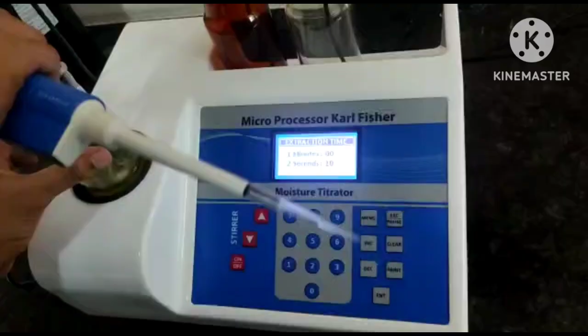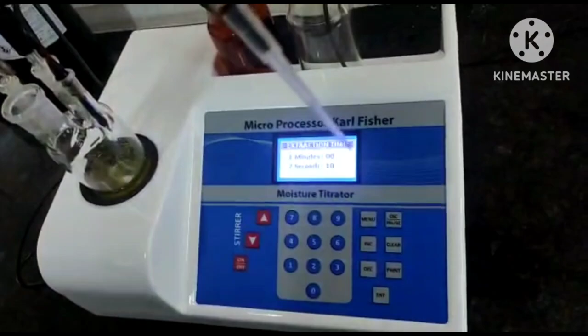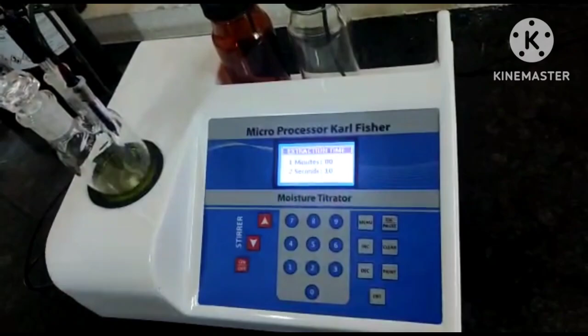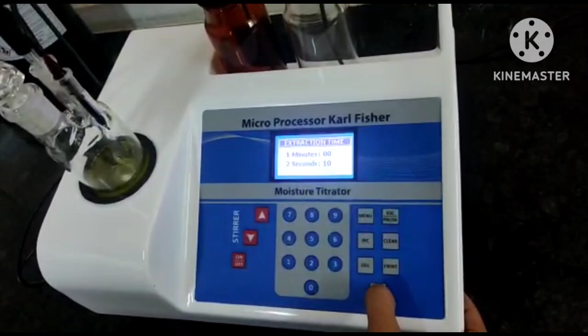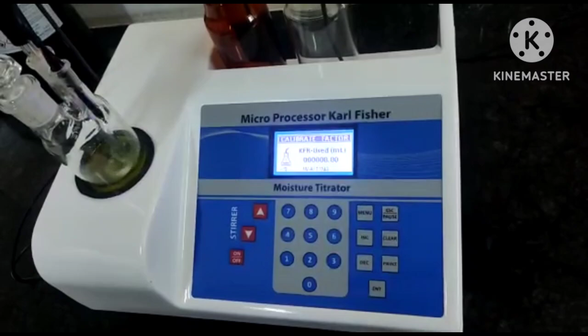To pour 25 microliter, I have taken 25 microliter. So we have to pour inside, and thereafter what you have to do, we have selected 10 seconds, that is okay for distilled water. It can get extracted within 10 seconds. So there we have to press enter. After that, you will get a message, we have poured inside the distilled water. Then we have to press enter.